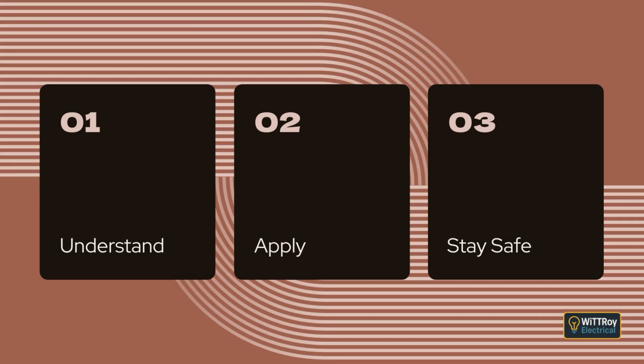Clause 7.2.3.4, Special lifts. This clause states that each lift or group of lifts that must operate for firefighting or for other emergency purposes must be controlled and protected independently of all other lifts. Clause 7.2.4, Arrangement. Clause 7.2.4.1, Supply. This clause explains that main switches for safety services must be connected on the supply side of all general installation main switches, must not be controlled by them, and must control only equipment regarded as safety services.